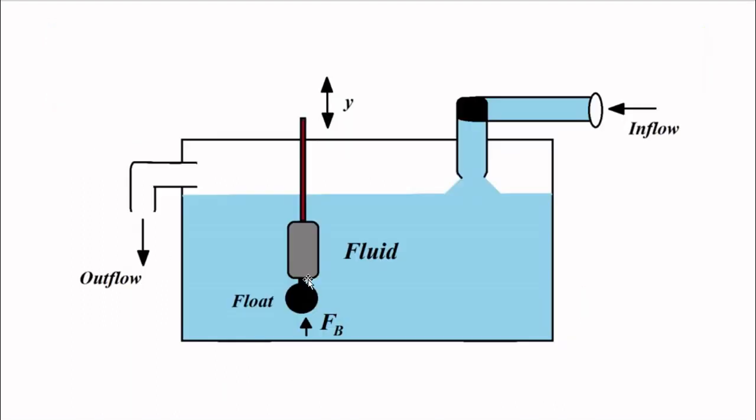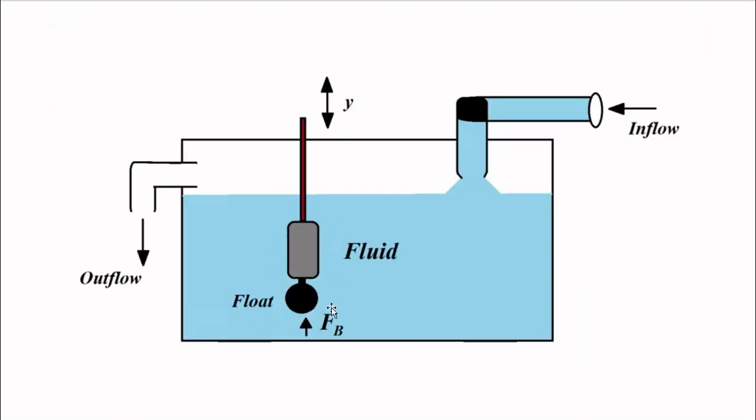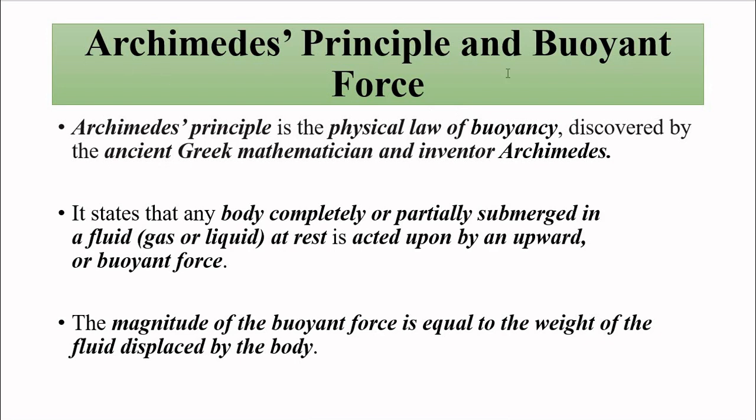This causes linear displacement of the stem attached to the float that can be connected to either secondary transducer, capacitive, inductive, LVDT, potentiometer, resistive, whatever. Or it can be connected to a simple pointer scale arrangement and can be calibrated to get a direct readout in terms of density. Because buoyant force is in direct relationship with density of the fluid. V_f and g are fixed. This is the basic operating principle of the hydrometer system for the measurement of density which employs float stem arrangement. It operates on the principle of buoyant force and Archimedes principle.